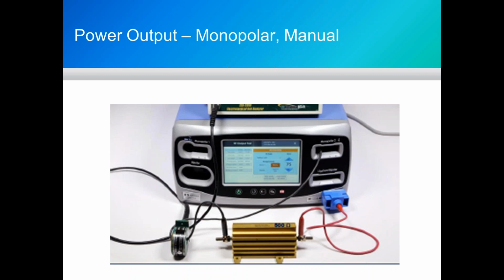So we went from an active output, a wire through the center of the current transformer, through our resistor, back to our patient return, and then the output port of that current transformer went up to what amounted to a digital voltmeter, high accuracy digital voltmeter, but a digital voltmeter nonetheless, and we would be looking at current that way. A universal test process, no doubt.